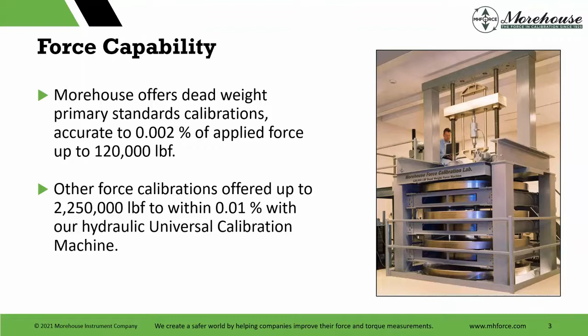So in our force calibration lab, we offer both force and torque calibrations at a very high level of accuracy. We are a primary standards laboratory and offer deadweight calibrations up to 120,000 pounds of force that's known to within 0.002% of applied force. And we also offer other force calibrations up to 2.25 million pounds or 10 meganewtons of force, which is known to 0.01% of applied force. In addition to force, we also have a torque standard. It's the most accurate and the second most accurate in the world, which was purchased from the National Physical Laboratory in England. For torque, we have uncertainties of better than 25 parts per million.